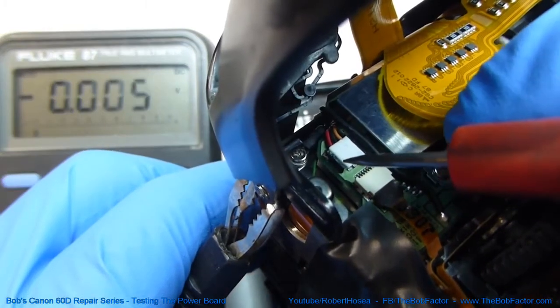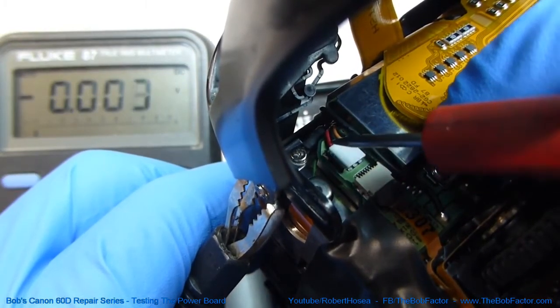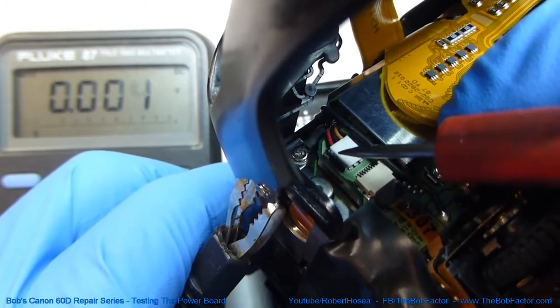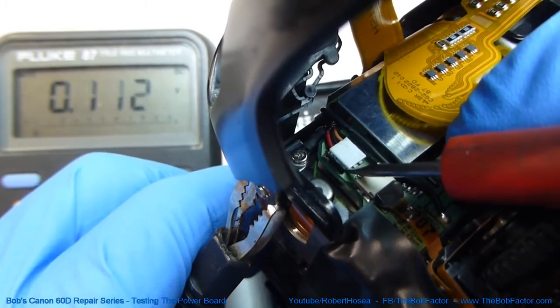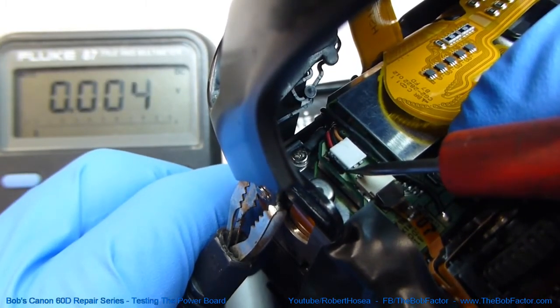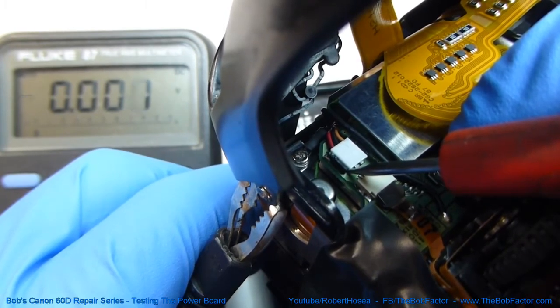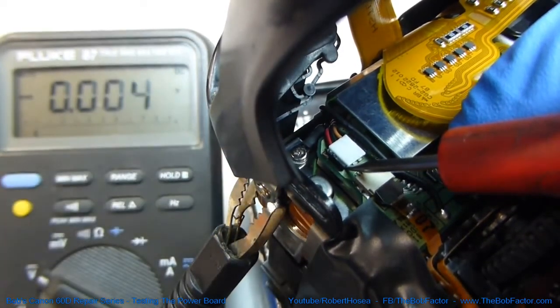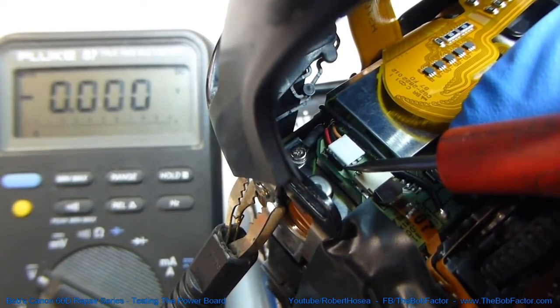On the connection on the far left side of the plug, which goes to a red wire, when we test it there, we can get a reading anywhere from 0 to 4.75 volts. And we can see right now it's pretty much at 0 volts.